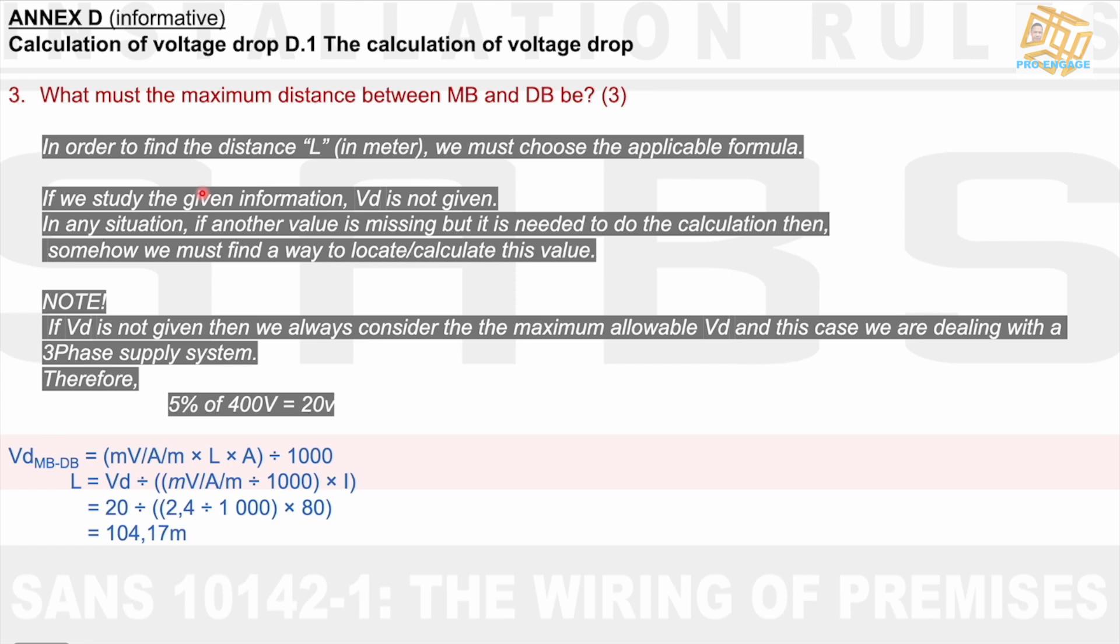Note, if VD is not given, then we always consider the maximum allowable voltage drop. And, in this case, we are dealing with a three phase supply system. Therefore, 5% of 400 volts equals 20 volts. Now, we need to manipulate this formula to make L the subject. Firstly, we use a formula VD equals MVAM times L times A divided by 1000. We manipulate the formula and VD then divides by MVAM divided by 1000, all of that times I. Your formula would be 20 over 2.4 divided by 1000, and that answer there times by 80. We divide that into 20 and we get a distance of 104.17 meters.